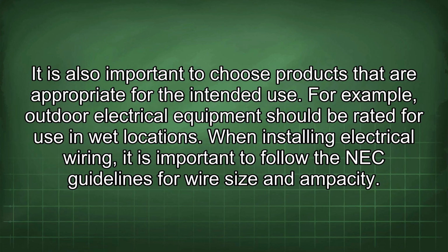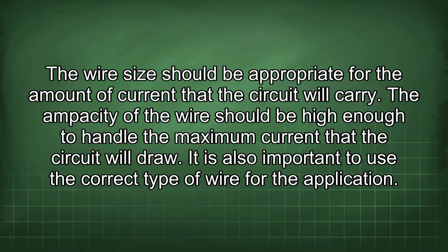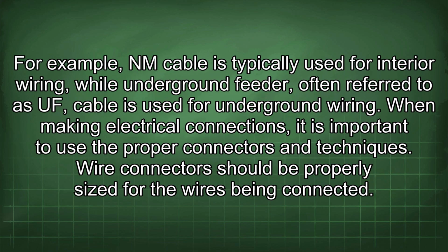When installing electrical wiring, it is important to follow the NEC guidelines for wire size and ampacity. The wire size should be appropriate for the amount of current that the circuit will carry. The ampacity of the wire should be high enough to handle the maximum current that the circuit will draw. It is also important to use the correct type of wire for the application. For example, NM cable is typically used for interior wiring, while underground feeder, often referred to as UF cable, is used for underground wiring.